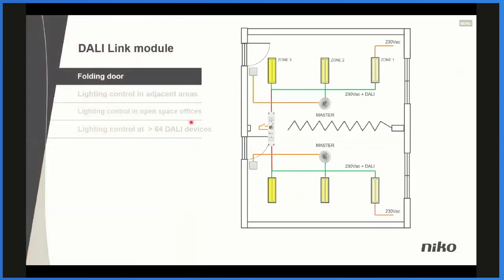Actually, how it operates is that if you have a folding door and there is a master detector in each of the two rooms, and between them we have a folding door. You have a kind of magnet here, and you have a switch over here, and it is connected to the DALI module that we have here. The DALI module is connected to the DALI buses on each side of the folding door. That means the DALI module is powered by either this master or this master. So if we are entering this room and you switch on the light, and if the folding door is open, the light will switch on in this room and in this room as well.